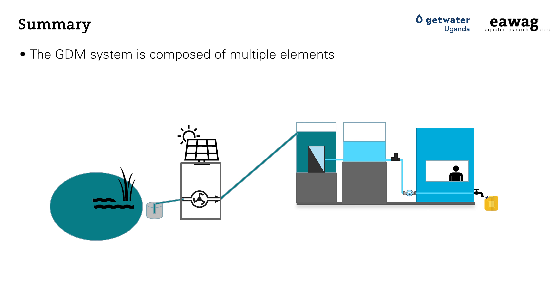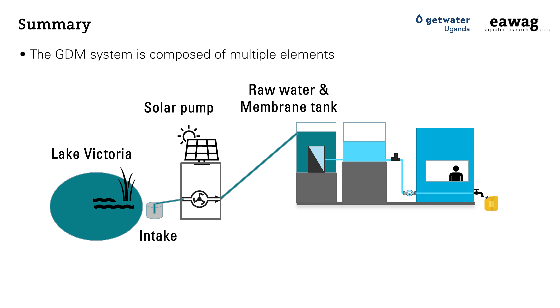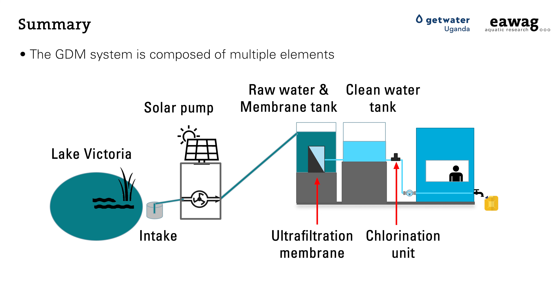This video has taught you how the GDM systems in our kiosks in eastern Uganda are composed. Water from Lake Victoria is pumped with solar power to the treatment site, where it is treated with a GDM filter and stored in the clean water storage tank. The ultrafiltration membranes of the GDM filter remove turbidity and pathogens. After the clean water storage tank, the water is chlorinated to protect it from recontamination. Customers can access the water 24 hours a day at the tap of the water kiosk via the water ATM.